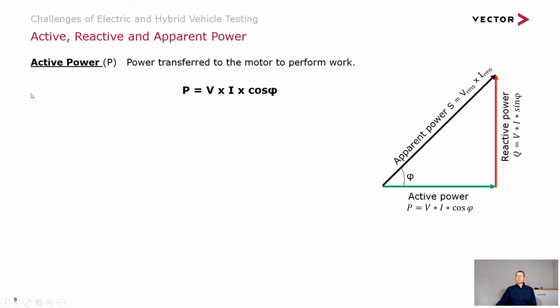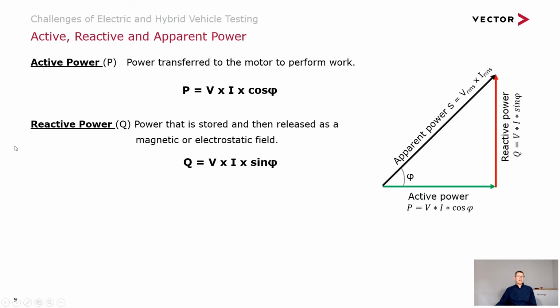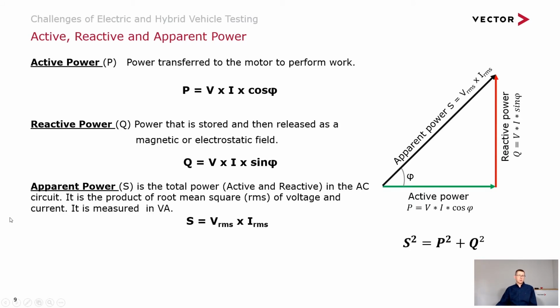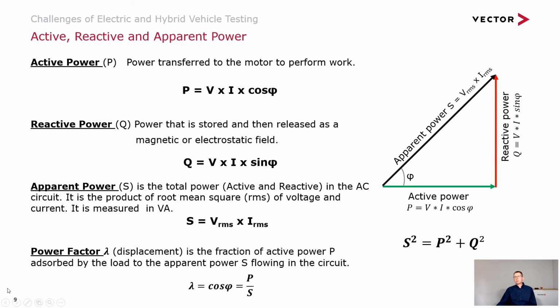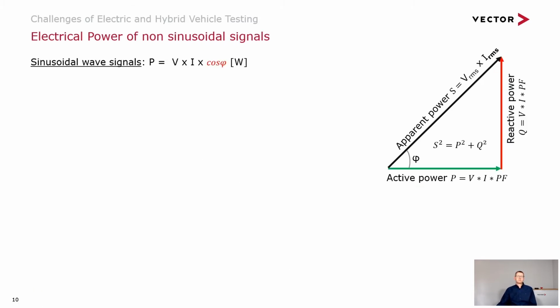So we have active power, which is the power transferred to the motor to perform work. We see that formula there. We then have reactive power, power stored and released as a magnetic field or electrostatic field. That's a sine of the phase difference. We then have apparent power, which is the active and reactive powers as a root mean square calculation. And then for your electric motor, for instance, you have a power factor, which is the active power over the apparent power as a percentage. So these values can be calculated with the right equipment.